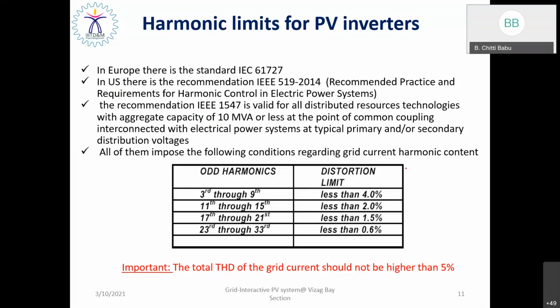So whatever control technique we propose on this inverter, it has to respect certain harmonic limits for the PV inverter. In Europe, there is a standard called IEC 61727. In the US, there is a recommendation, the IEEE 519-2014 standard. It is meant for recommended practice and requirements for harmonic control in electrical power systems. In addition, there is another important standard, IEEE 1547, for distributed energy resources integration with capacity up to 10 MVA.